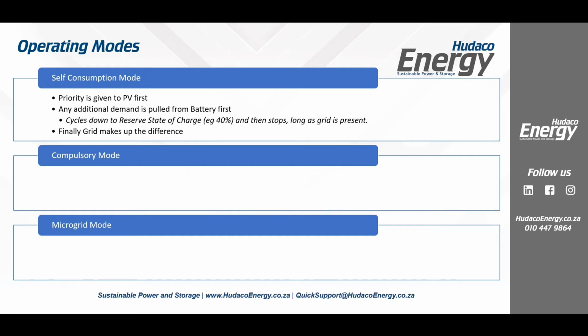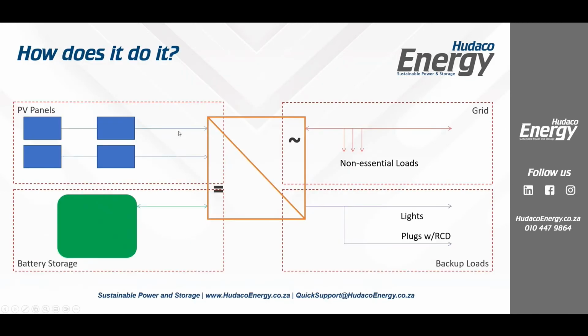And that available battery size, you can set yourself. You could, if you wanted to, set it from 5% to 95% for whatever reason, but 100% is fine. You also have the option to do a reserve state of charge. What a reserve state of charge setting does is, even though with 16 we may have 16 kilowatt hours that we're allowed to use on the battery, you may put a reserve state of charge in, which could be, say, a 40% level.